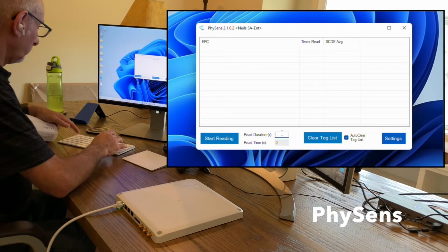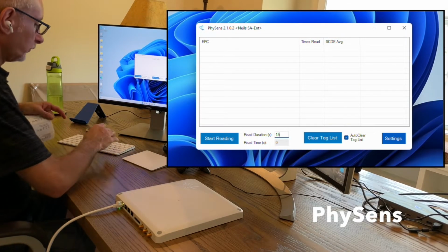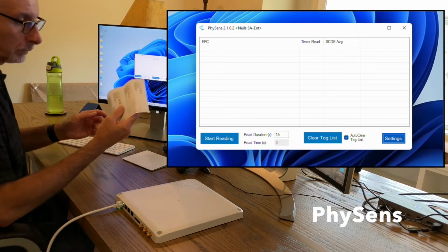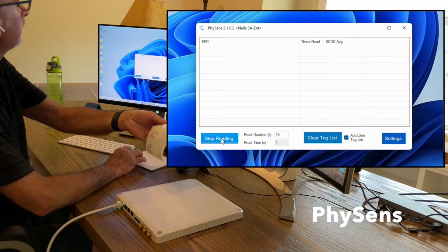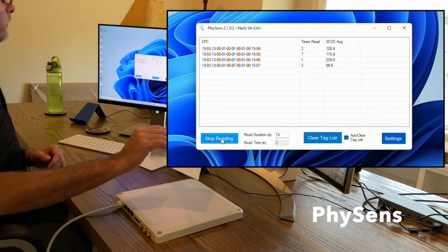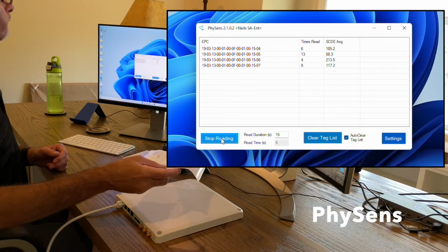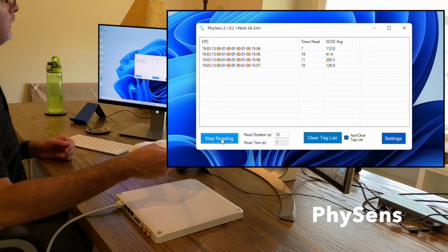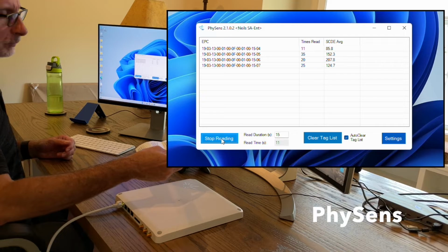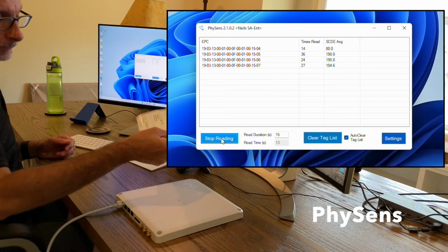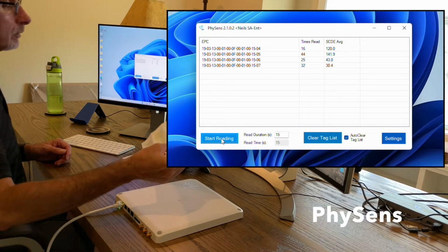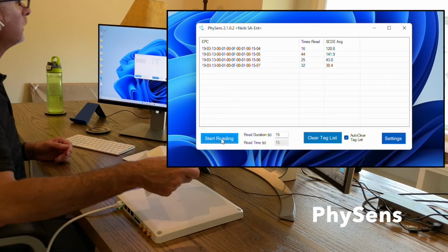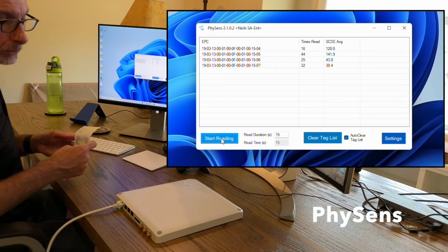Okay, and so I'm just going to go ahead and read some of these tags for reading moisture. So if I start reading, you'll see them being reported right here. And the averaging will start to bring the values close together. The fact is I'm holding a couple of them here, which probably makes them read a little bit funny because they're reading the density of my hands as well. But you can see the reporting there quite happily.